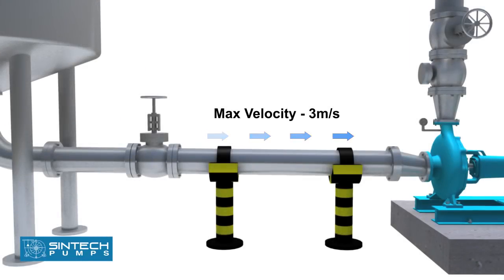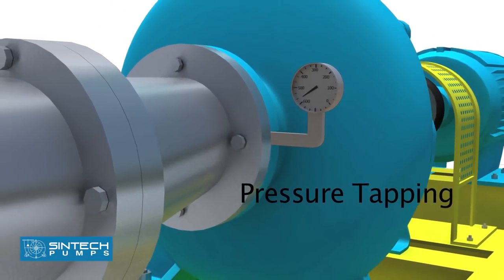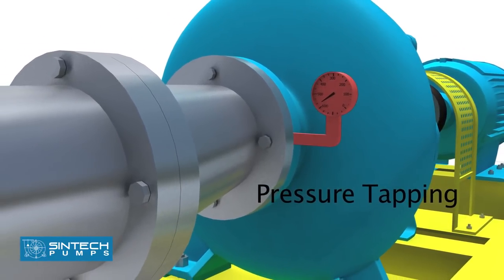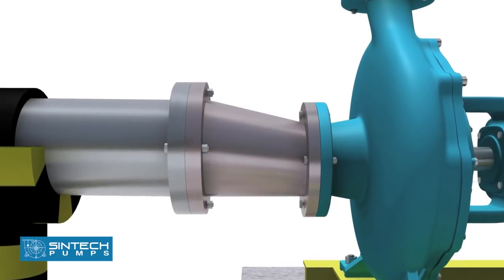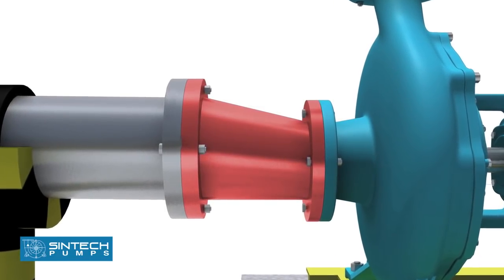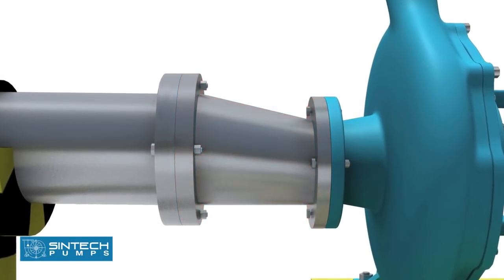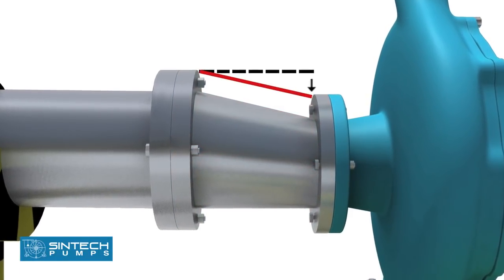The suction pipe should be sized to ensure a liquid velocity of not more than 3 meters per second. There should be a tapping provided for installing a pressure gauge in the suction line. The reducer joining the straight length of the pipe in the pump line should be an eccentric reducer with the inclined side of the reducer as the top side.